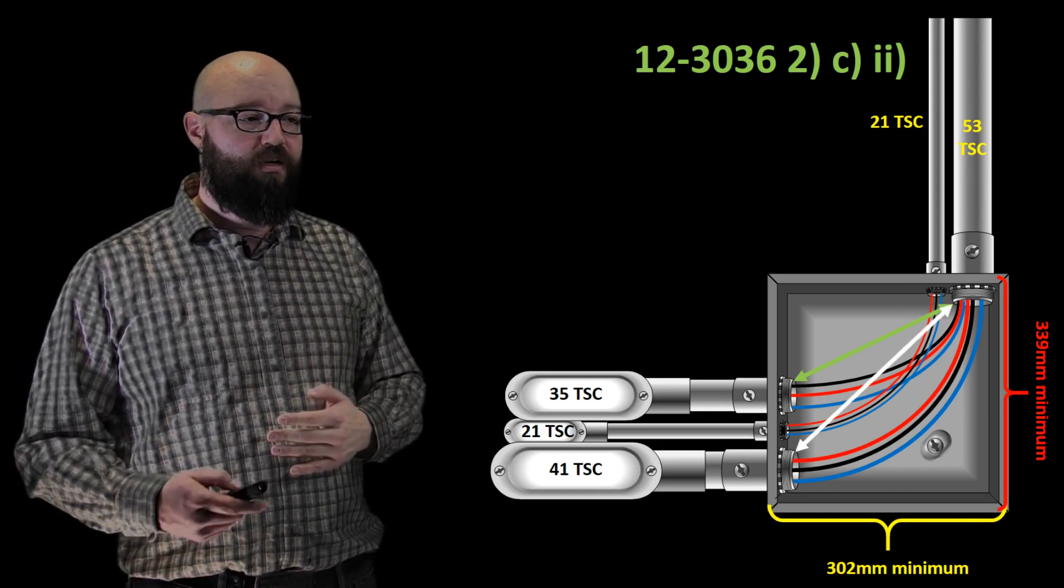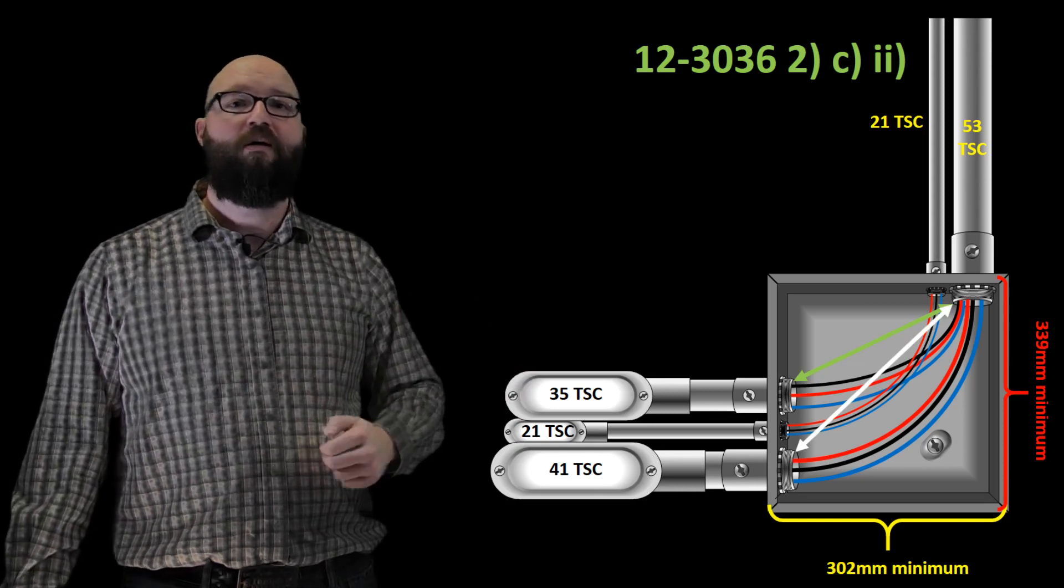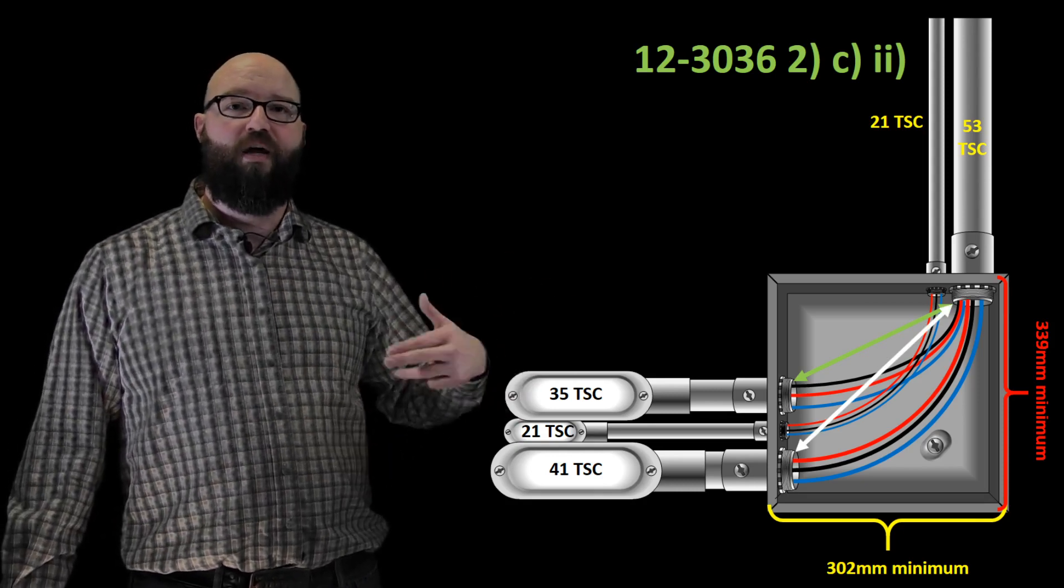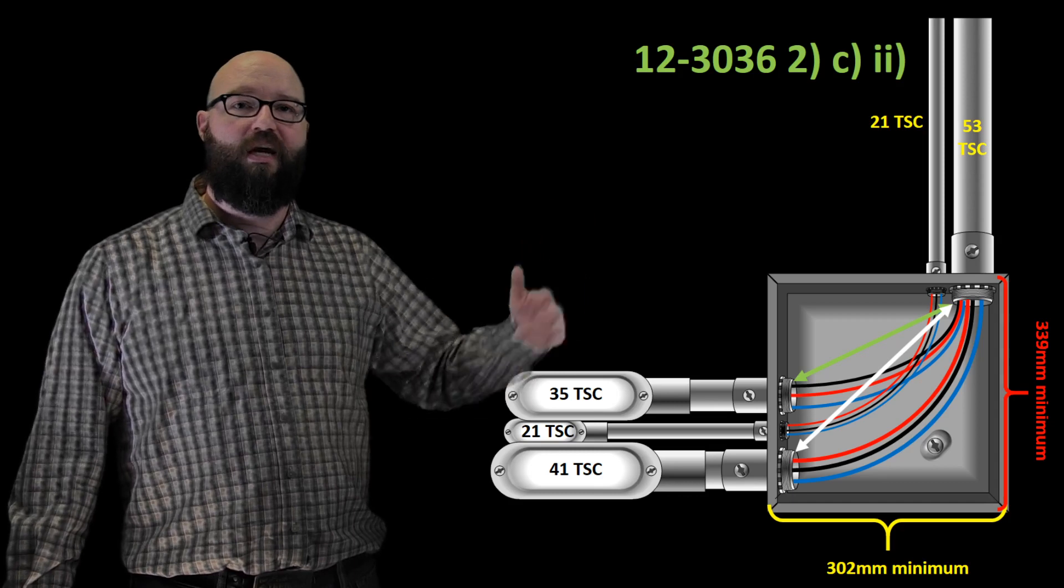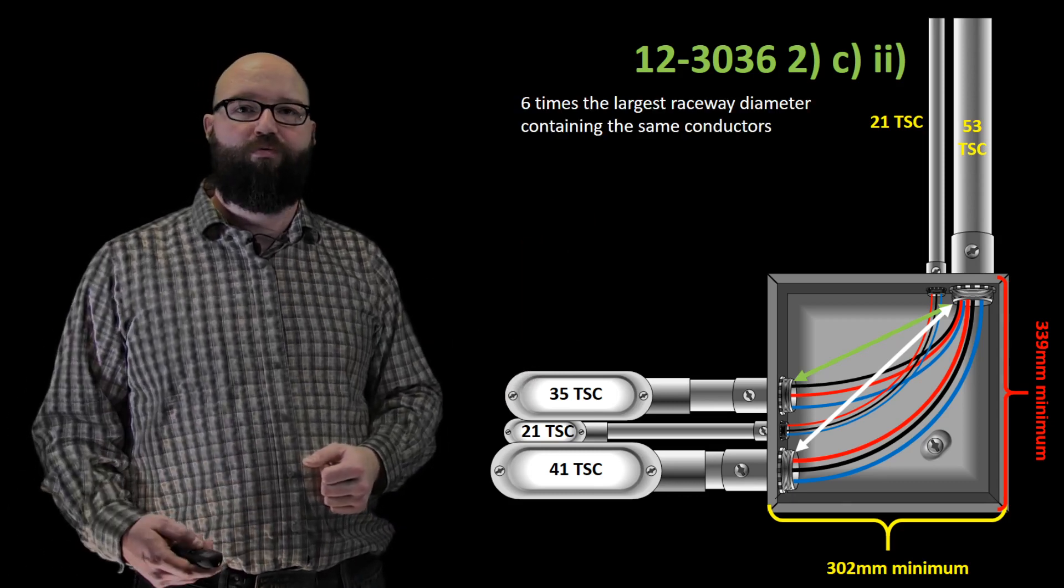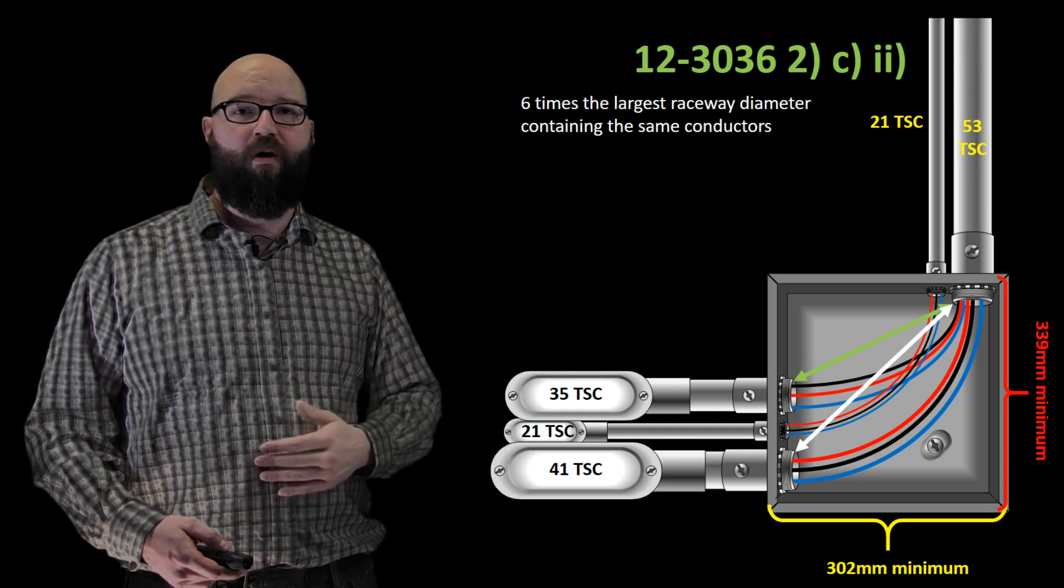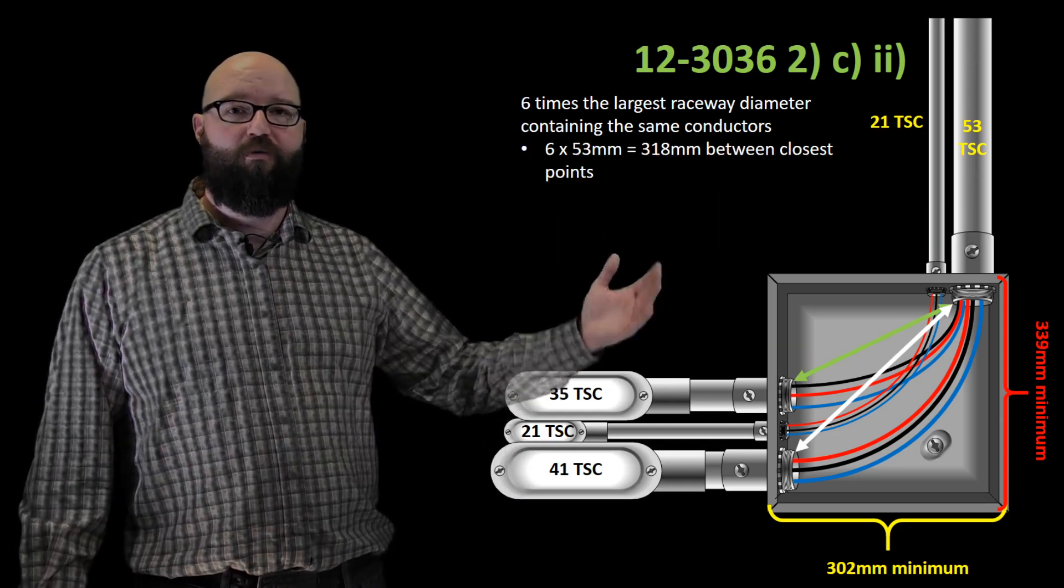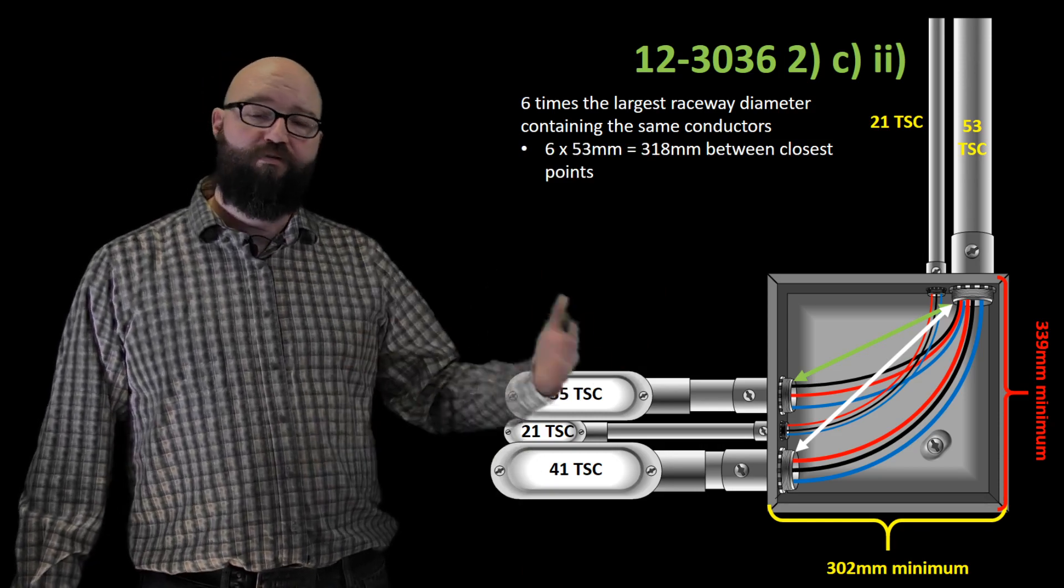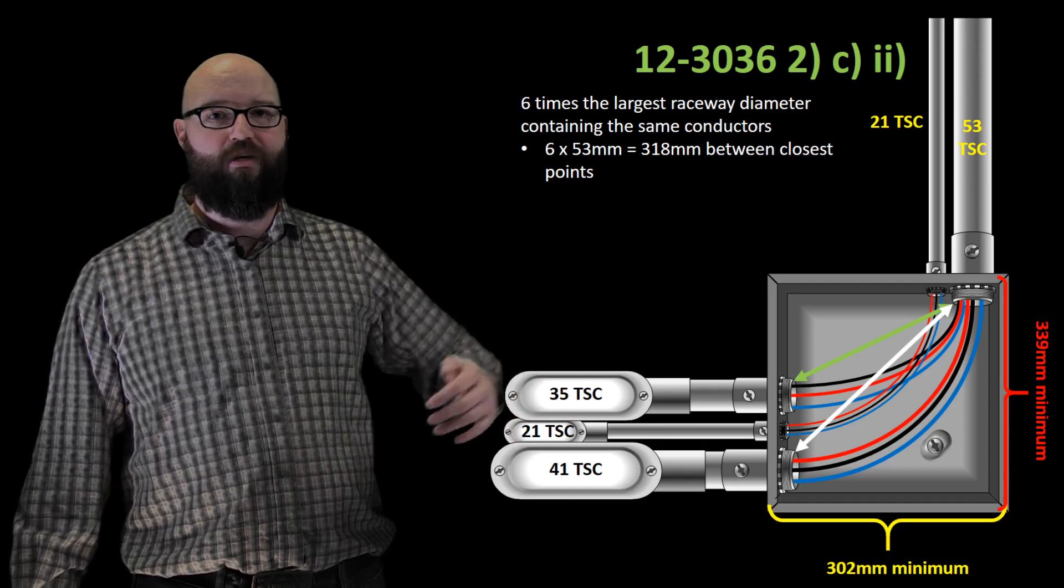And if we look at the next conduit as well, same thing, the minimum distance between those two points would again be six times the largest diameter of the raceway containing those two cables. So again, it would be the exact same. We would take that 53 trade size conduit. We have 53 and 41 that we're comparing. 53 trade size conduit times 6 gives us again the 318 millimeter distance minimum between those from the inside edges.